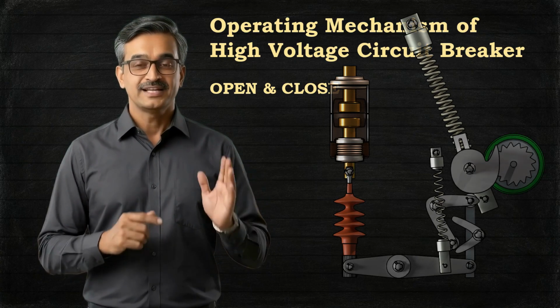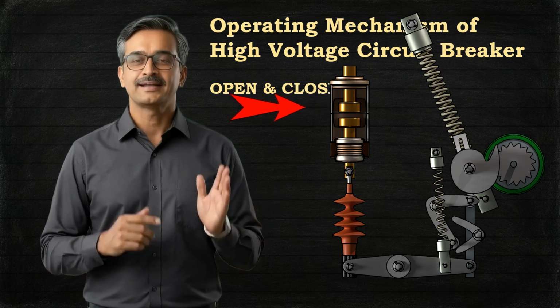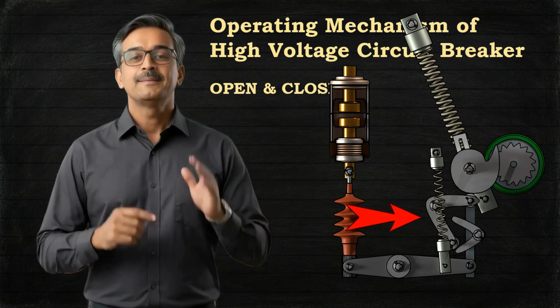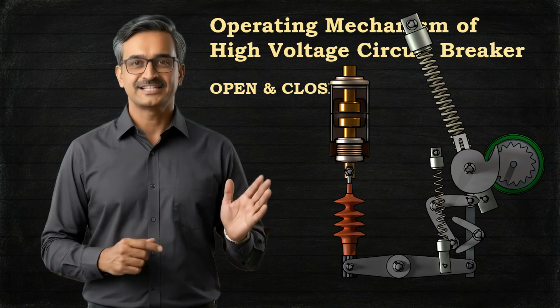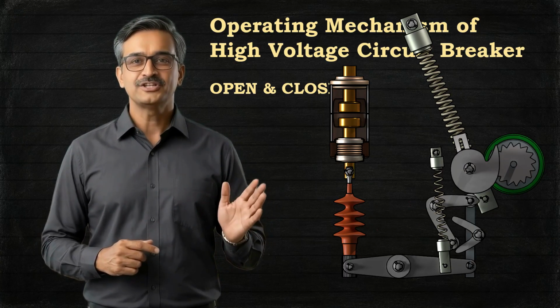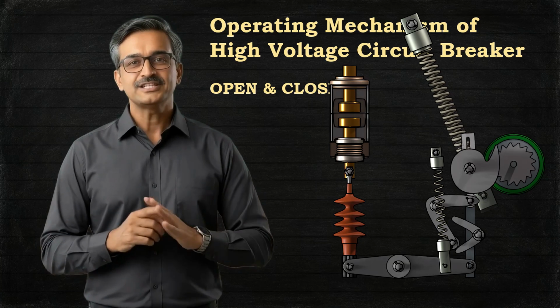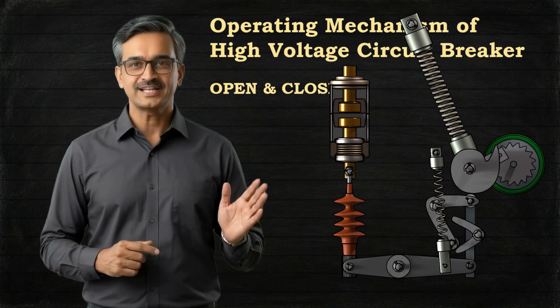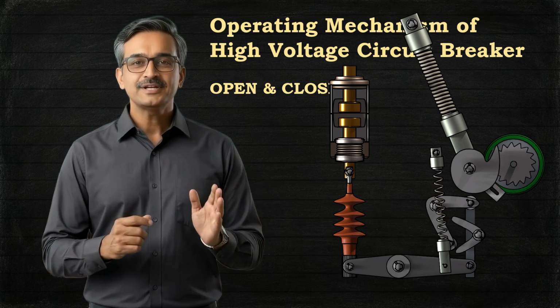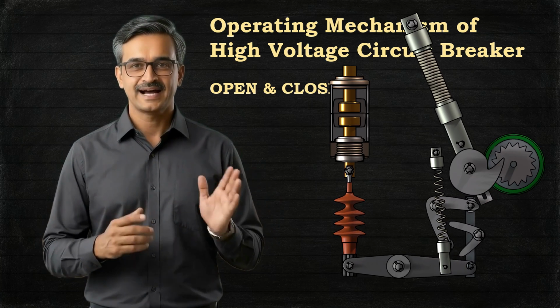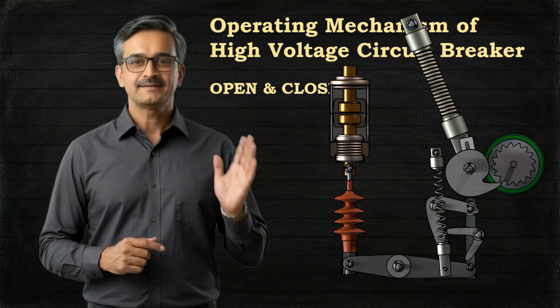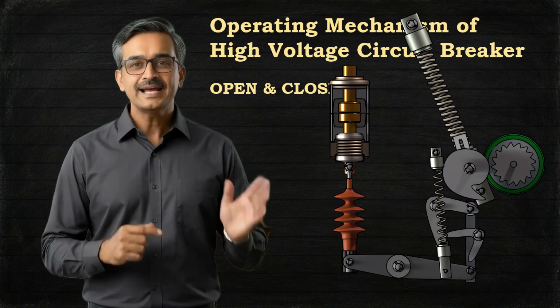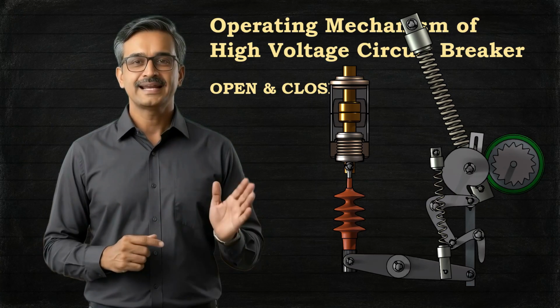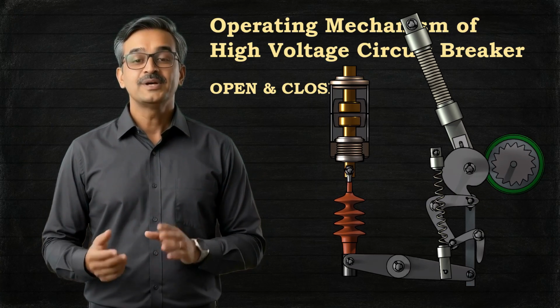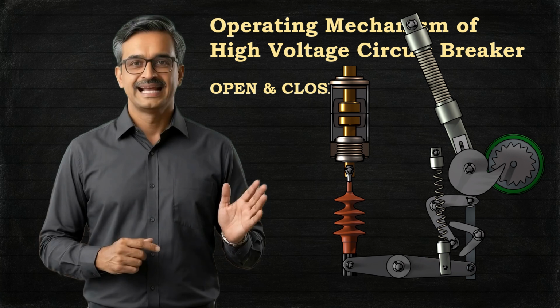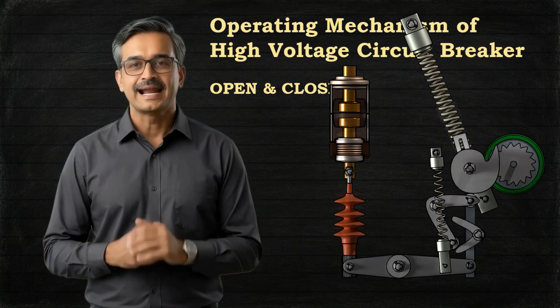This is the fixed contact, and this is the moving contact. This is the operating linkage assembly. The entire moving assembly has considerable weight. Now suppose a short circuit develops in the system. Within just a few milliseconds, this heavy moving contact has to accelerate from rest, travel a certain distance, extinguish the arc, and completely isolate the faulty circuit. Obviously, a very large amount of mechanical energy is required for this operation, and equally obviously, it has to be available instantly. So naturally, the next question is, where does this mechanical energy come from?